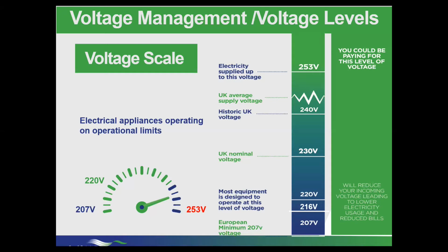For about 10 years now, we've been looking at a voltage where everything is designed at the same level, which is 230 volts. But in reality nothing has changed - our nominal voltage that we still operate at is 240, and the average is 242. Compared to the voltage level in mainland Europe, where the highest is 243, our average is only 1 volt below, yet we can go all the way up to 253, and commonly do.